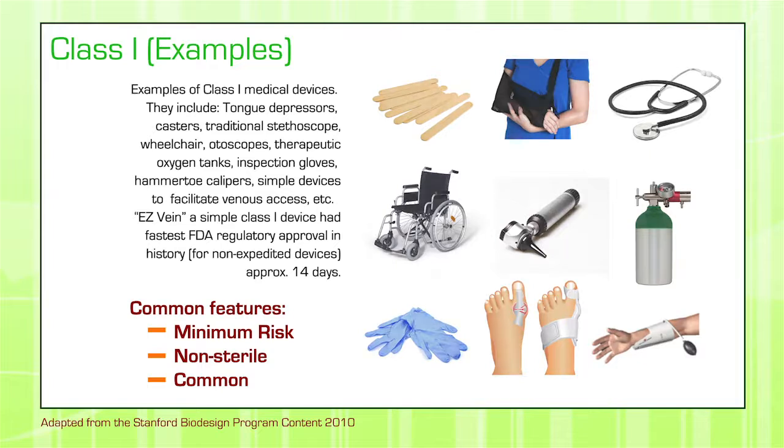As you may notice, this is a non-invasive, a minimum risk, a fairly simple device that has a clinically relevant impact, and it was classified as class 1 because of all these characteristics. So when you think about creating new medical devices, please try to take a look at solutions that actually are fairly known, and then try to see if you can come up with an idea that meets those requirements of non-invasiveness, minimum risk, and common manufacturing processes, so that you can enter into this space, which is fairly easy to enter.